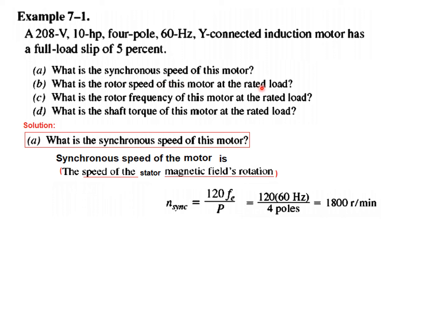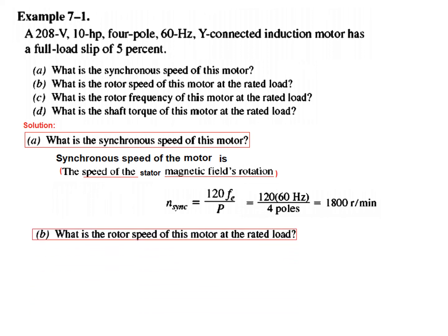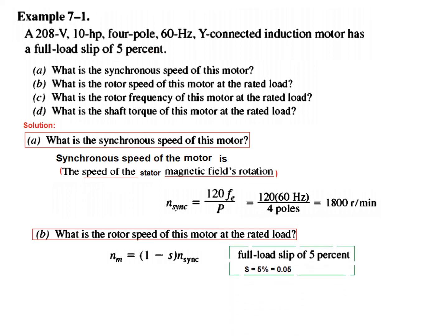Now we find the rotor speed. The rotor speed lags, and using the formula N_m = (1 − S) × N_sync: the full-load slip is 5%, so S = 0.05. Plugging in N_sync = 1800 RPM, the rotor speed is 1710 RPM. You can see that the stator magnetic field speed and the rotor speed are different — the rotor is lagging N_sync.